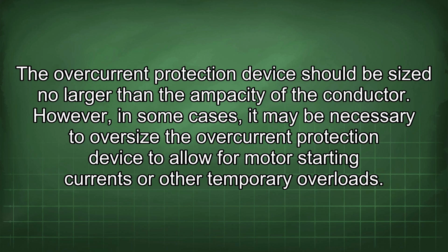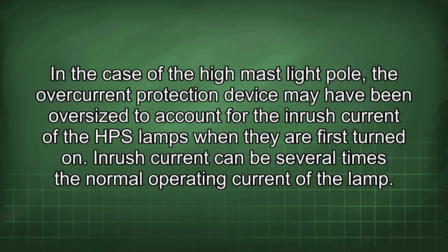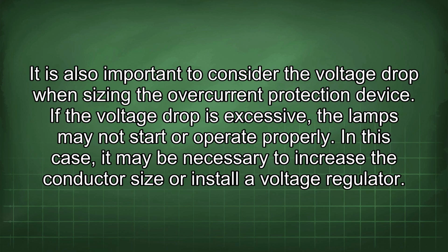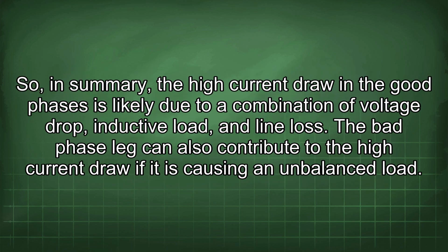However, in some cases, it may be necessary to oversize the overcurrent protection device to allow for motor starting currents or other temporary overloads. In the case of the high mast light pole, the overcurrent protection device may have been oversized to account for the inrush current of the HPS lamps when they are first turned on. Inrush current can be several times the normal operating current of the lamp. It is also important to consider the voltage drop when sizing the overcurrent protection device. If the voltage drop is excessive, the lamps may not start or operate properly. In this case, it may be necessary to increase the conductor size or install a voltage regulator. So, in summary, the high current draw in the good phases is likely due to a combination of voltage drop, inductive load, and line loss.